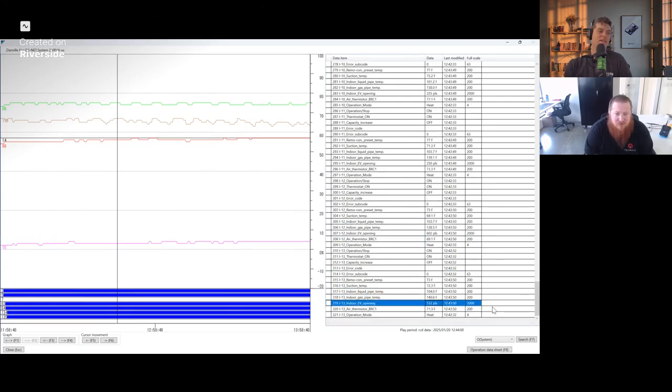Largest. So he is saying the unit that is getting the most refrigerant, right? Because remember, all these valves are the same size, guys, right? Depending on where they're connected in the system. Could be longest, could be furthest, could be shortest. Just because it's at the bottom of the list doesn't mean it's the last connected unit. Don't make that assumption, because you would be wrong.